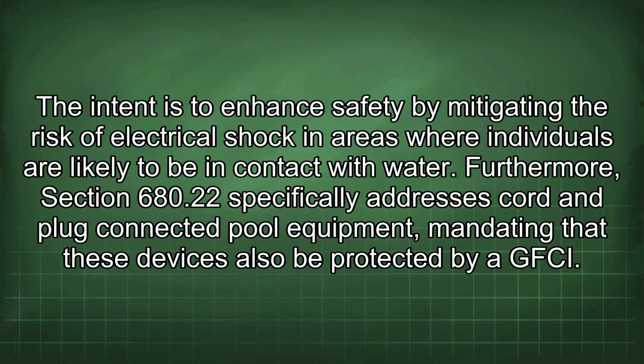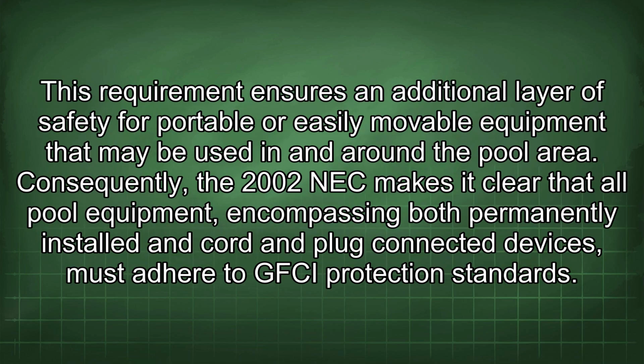Furthermore, Section 680.22 specifically addresses cord and plug-connected pool equipment, mandating that these devices also be protected by a GFCI. This requirement ensures an additional layer of safety for portable or easily movable equipment that may be used in and around the pool area. Consequently, the 2002 NEC makes it clear that all pool equipment, encompassing both permanently installed and cord and plug-connected devices, must adhere to GFCI protection standards.